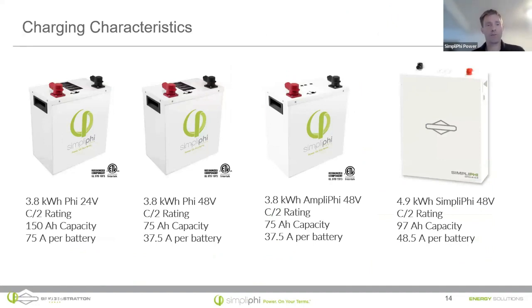The charging characteristics of our batteries are specified here. I'm just showing you our most common batteries. A 3.8 kilowatt hour Phi battery in 24 volts has 150 amp hour capacity. All of these batteries are rated at C/2, so half of 150 amp hours would be the C/2 charge rate. So we can charge that battery at 75 amps. Now, if you have a battery bank with 3 batteries, and we always install our batteries only in parallel, never in series, then it would be 3 times 75 amps charging.